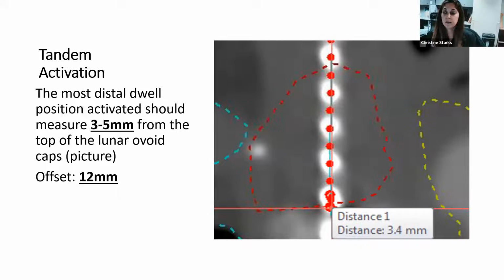Moving into tandem activation, here at the crosshair would be the top of the lunar ovoid cap. When we activate our dwell positions, each dwell position is going to be at 5 millimeters. And two, we don't want to activate closer than 3 to 5 millimeters from the top of that lunar ovoid. We know that the offset at the tip of the tandem is 12 millimeters. Keeping in mind earlier, whenever I put the system together, sometimes we'll also lose, as you're hooking the tandem to the ovoids, about 6 millimeters of distance as the tandem pulls back in the uterus.